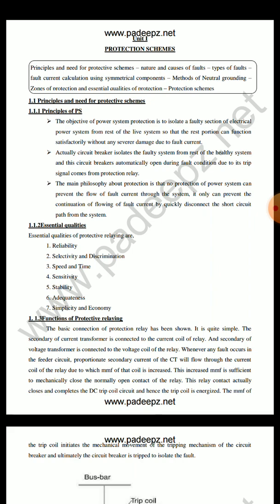So after the generating stage, we need to protect our generators also, because power supply variation or faults may occur. There are varieties of reasons. Even arc type of errors have the possibility to affect the entire setup, like bus bars and all. Once we generate the power supply, we need to step up the voltage, and then through the bus bar and transmission line, we need to transmit that power supply over a number of kilometers.